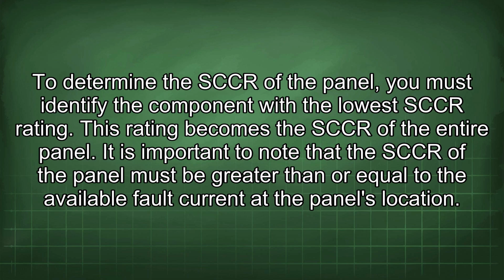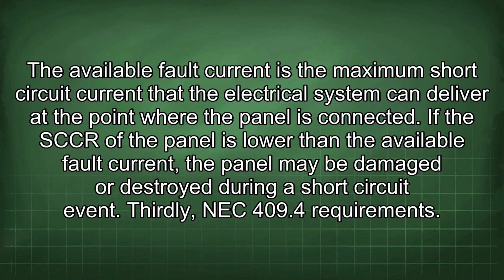It is important to note that the SCCR of the panel must be greater than or equal to the available fault current at the panel's location. The available fault current is the maximum short-circuit current that the electrical system can deliver at the point where the panel is connected. If the SCCR of the panel is lower than the available fault current, the panel may be damaged or destroyed during a short-circuit event.